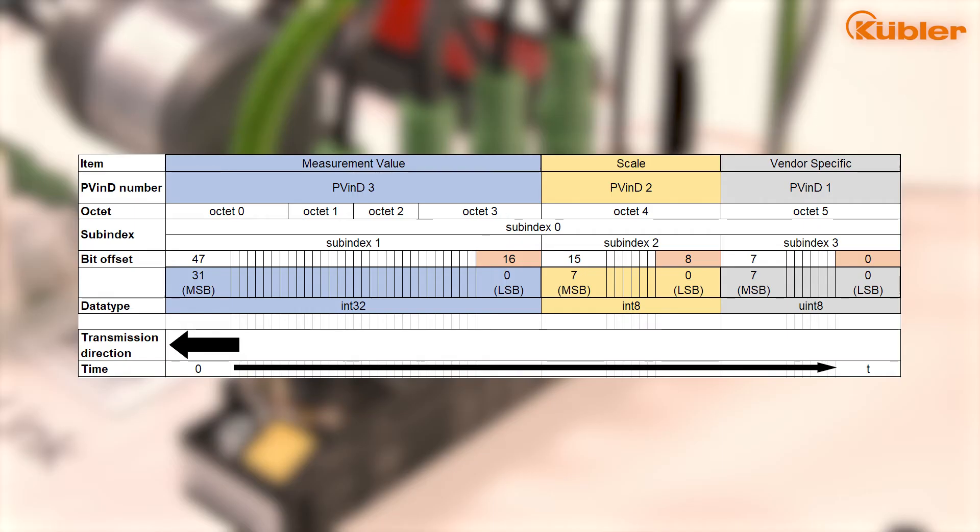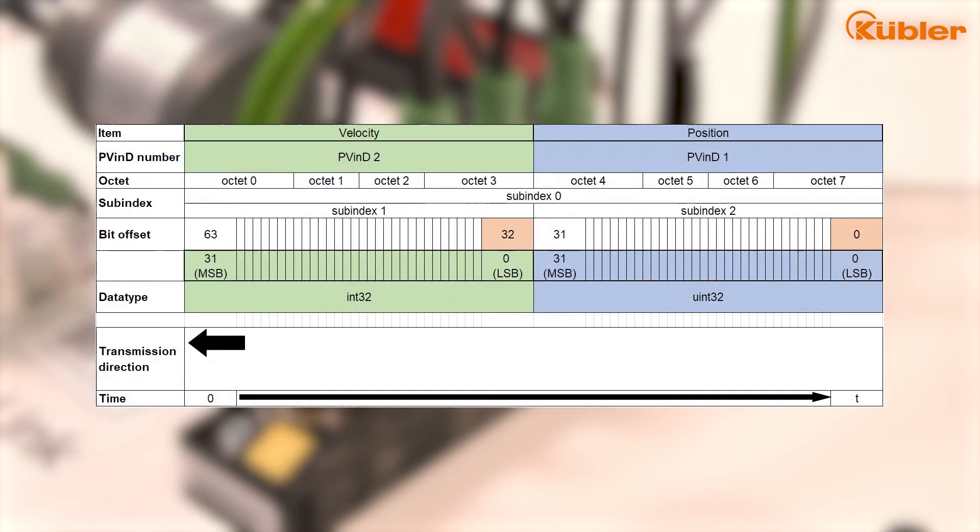The M36 IO-Link has two profiles from which you can choose. The first profile is the smart sensor profile. With this profile, a position value and a scaling factor are transmitted. With the second profile, the Kubler standard profile, a position and a velocity value are transmitted. Depending on your application, you can choose either one of them.